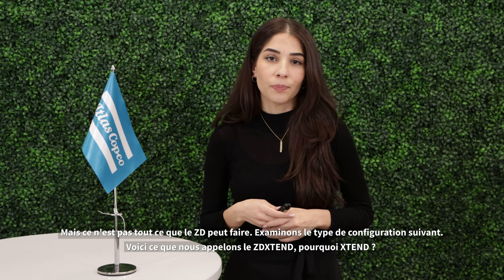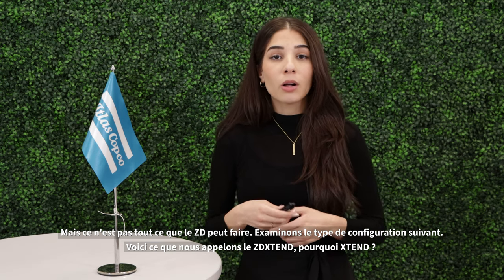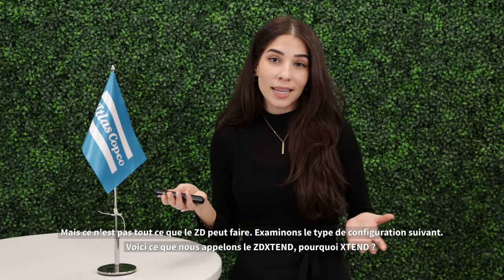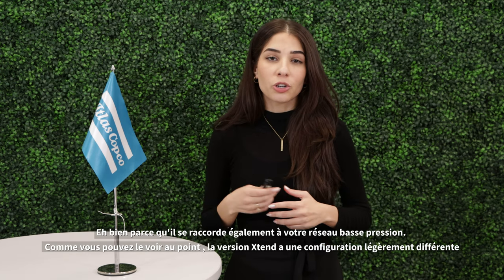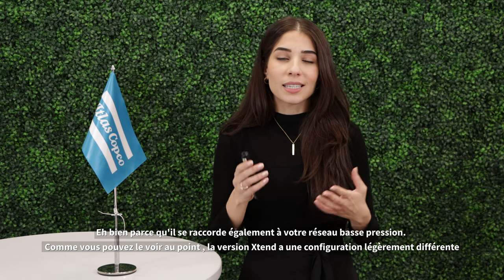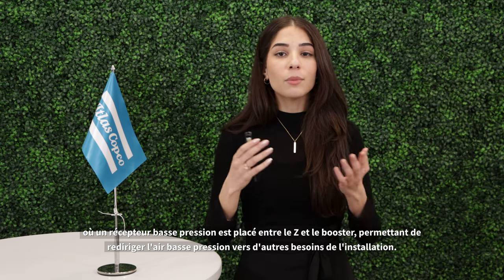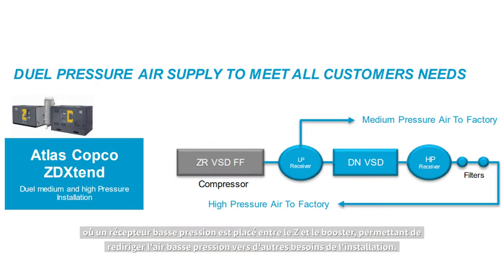But that's not all the ZD can do. Let's look at the next type of configuration available. Here is what we call the ZDXtend — because it extends to your low pressure network as well. The ZDXtend version has a slightly different configuration where a low pressure receiver will be placed between the ZD and the booster, allowing for low pressure air to be redirected to your other plant requirements.